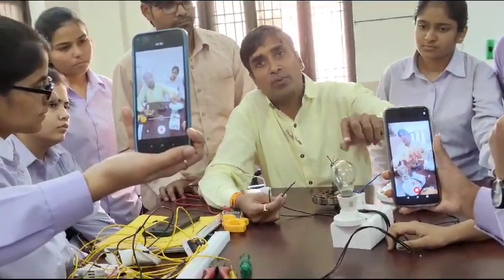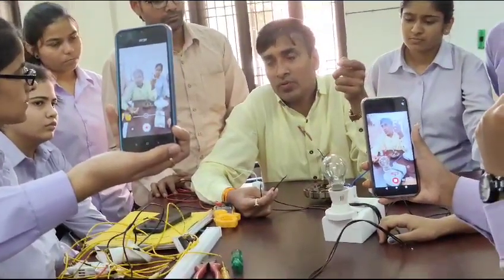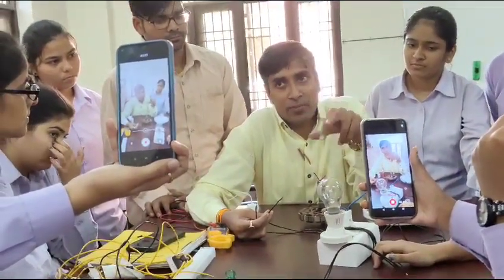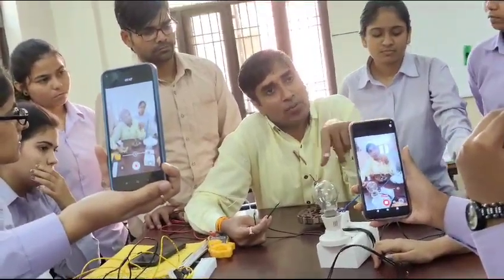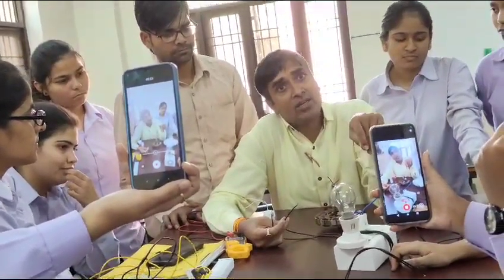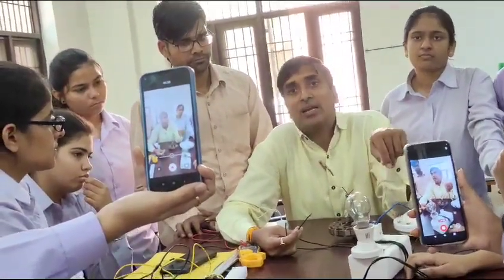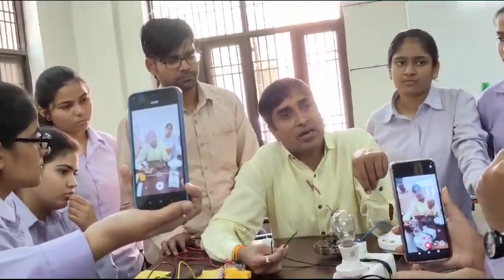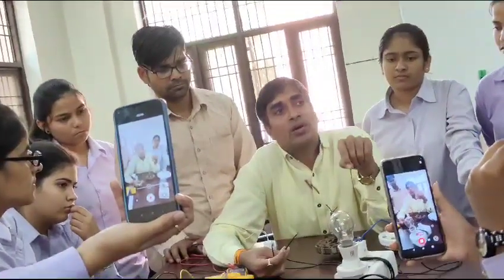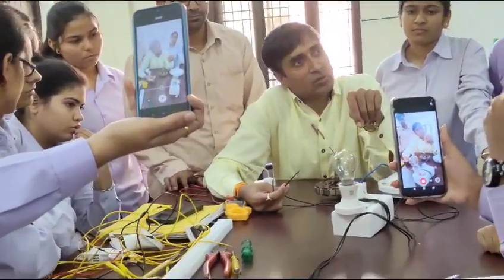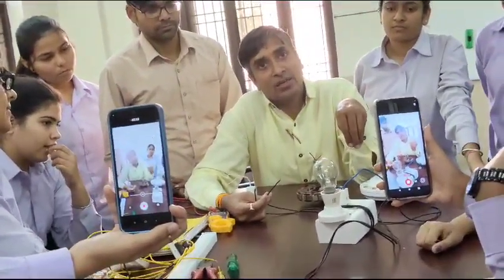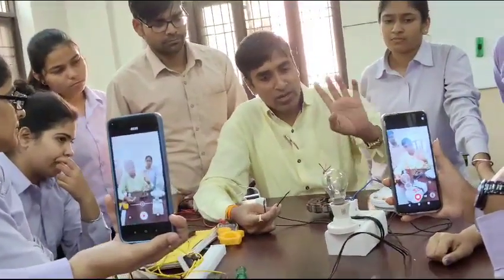For this we will use this bulb and see the intensity of glow. If we compare two cases, the brighter case is related to the running winding. Then we check between the running winding and starting winding, and there the glow is very less. There is a need to connect the capacitor. That will be given by the testing of this winding and of this capacitor, and after that we will check this capacitor. Is it okay? Yes, sir.